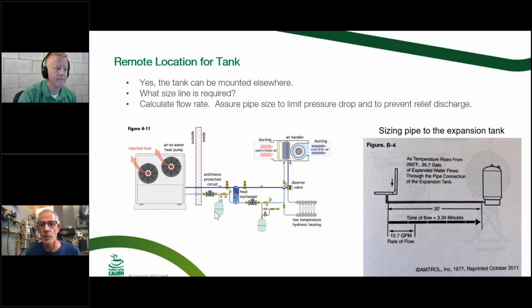Yeah, we'll go into that a little bit more in a couple of slides. So what I wanted to show there on the bottom right, on this picture, people ask, okay, what size does the pipe need to be between the expansion tank and wherever you connect it into the system, into the boiler? You have to get into a pretty big system before you have to start worrying about going beyond a half inch.